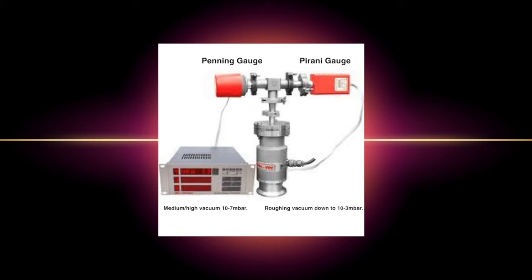A Pirani gauge works by a filament which carries a current and a heat sensor which measures thermal and radiative heat. The voltage or current is regulated to keep the temperature of the filament constant. As the vacuum system improves, less gas touches the filament and less current is needed to regulate the temperature of the filament. These changes in current are calibrated in the factory to correspond to different pressure readings. The Pirani gauge responds to pressure changes very fast.